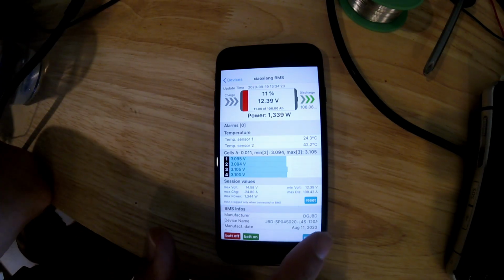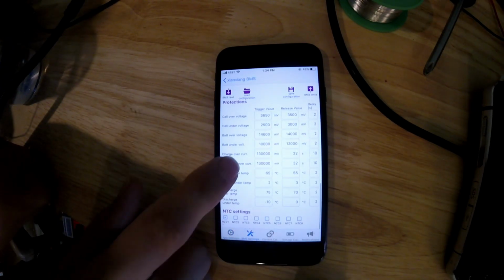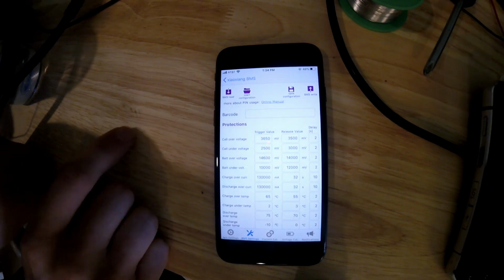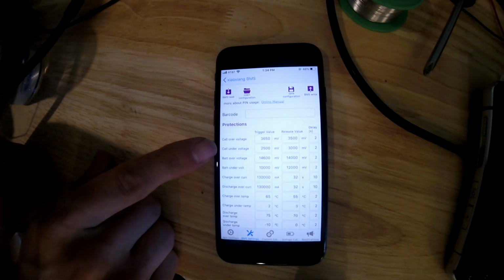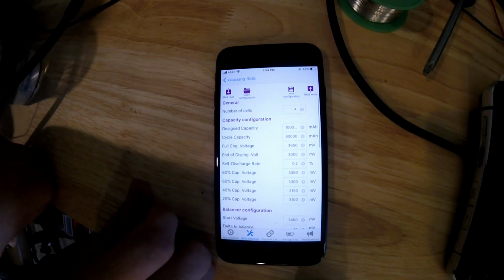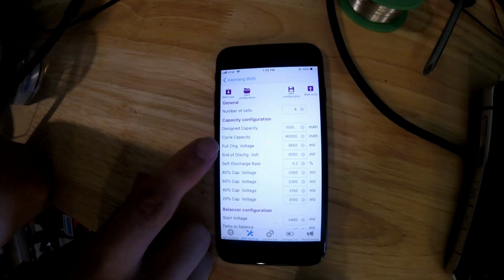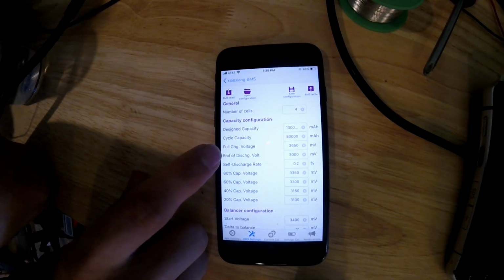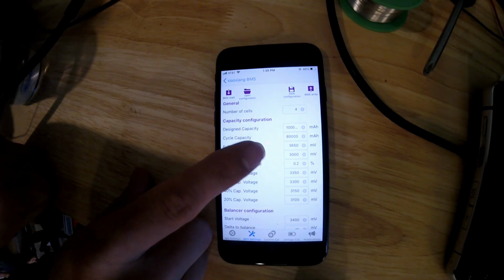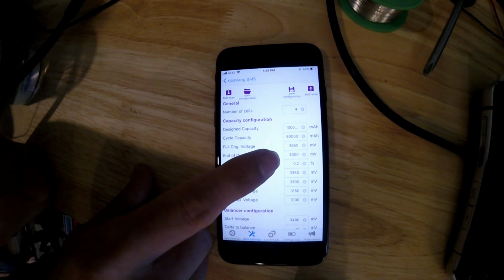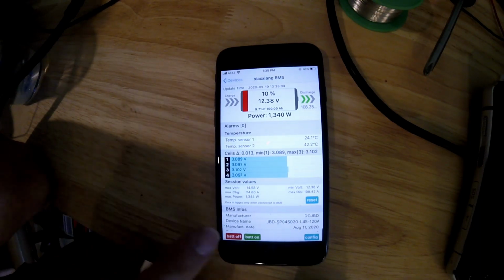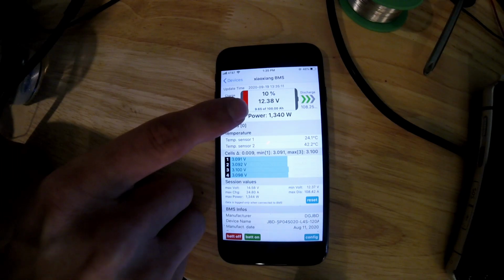Let's go check the config to see where our alarm is set. Our cell under voltage is set to 2.5 volts, so that's actually a ways before it gets to that point. But these batteries will drop off quickly after 3 volts. I have this set to a full charge voltage of 3.65 volts per cell, and an end voltage of 3 volts, which explains why we're reaching the very end here.